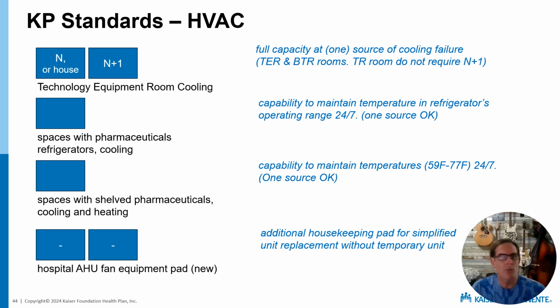We do not require redundancy or even partial capacity at equipment failure in the pharmaceutical areas, but we do require 24/7 planning. So even in a medical office building, if you have an area with shelved pharmaceuticals, then you need to be able to maintain that space between 60 and 80 degrees 24/7.